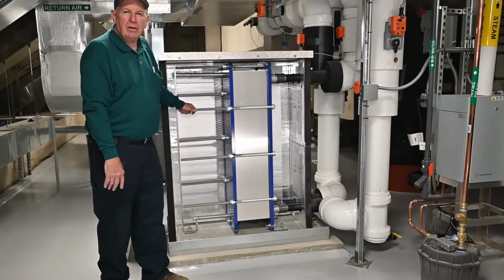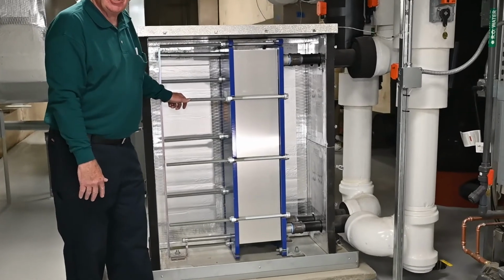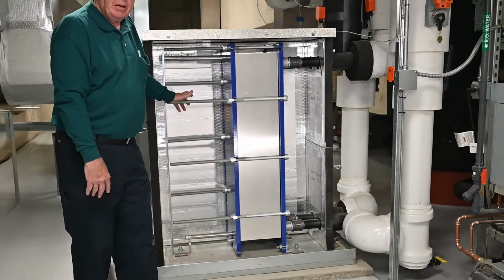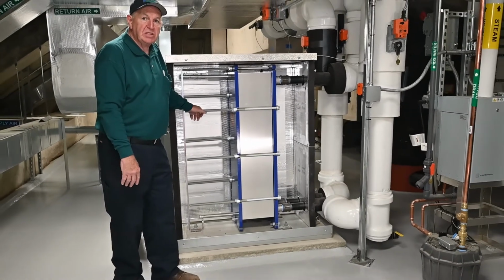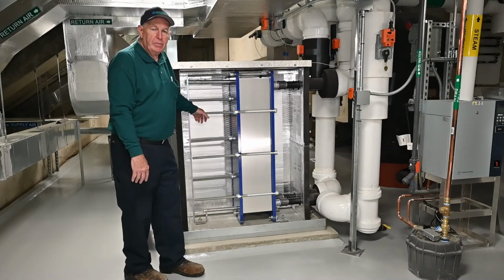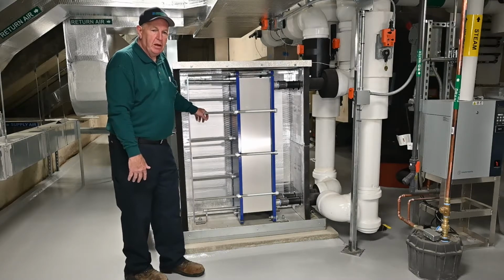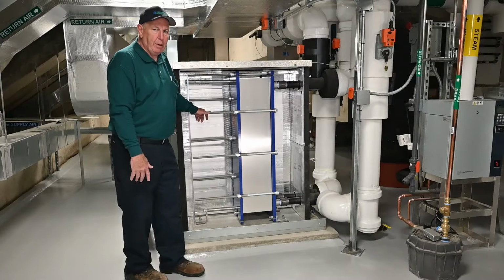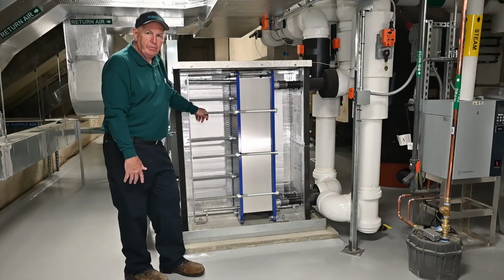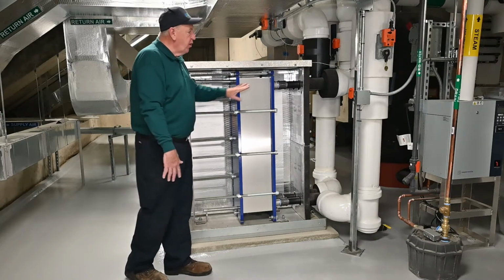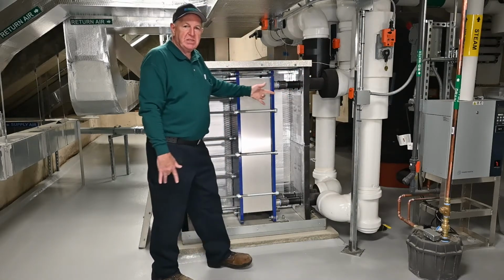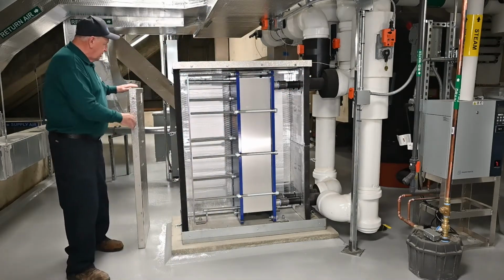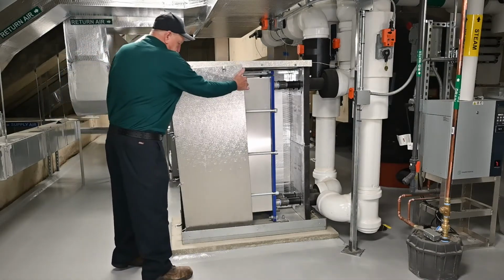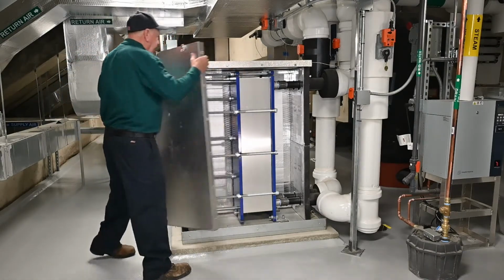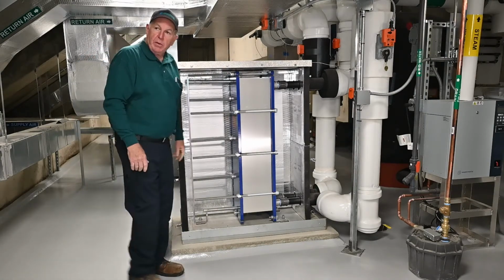Where we're using glycol, there's less chance of corrosion and plugging. But if you notice a reduced capacity, then it needs to be serviced, needs to be cleaned. But that's probably not going to happen very often here because of the glycol with the inhibitor in it. And this is fully automatic, so like I say, it's only a backup system. We have these insulated panels so that it won't sweat, and it's all hinged, and that's about it. Are there any questions?